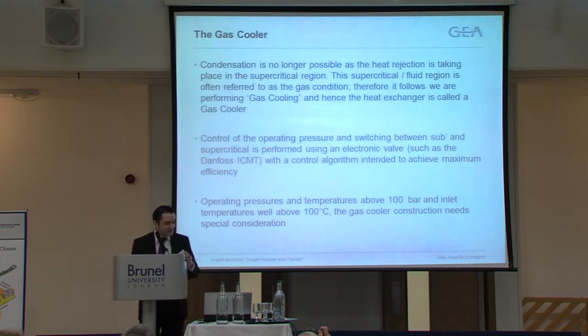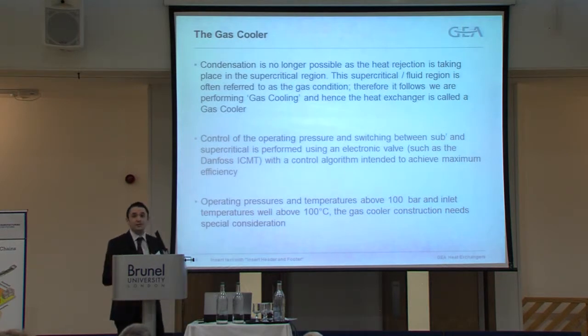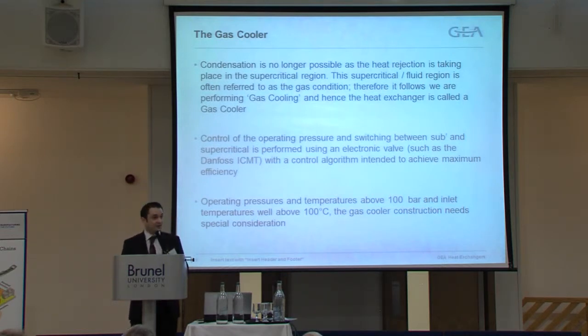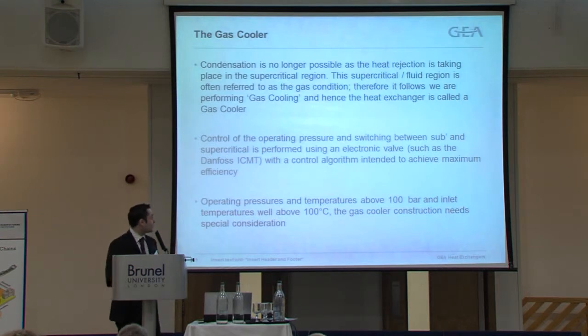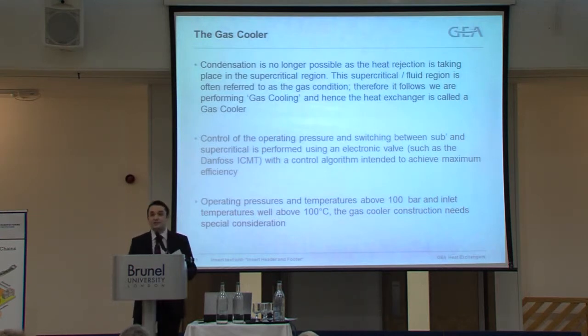So, in summary, condensation is no longer possible because heat rejection is taking place in the supercritical fluid region. Therefore, it's commonly known as the gas region, so it could be said we're completing gas cooling, hence the product's called a gas cooler. Now, control of the operating system between subcritical and supercritical is managed by a valve such as the Danfoss ICMT or the ICMTS, which they'll be speaking to you about later, I'm sure, which works off a control algorithm to ensure the system's always working at the maximum efficiency. Now, with operating pressures above 100 bar and inlet temperatures well above 100 degrees C, a conventional heat exchanger isn't the best bet, and the construction of the heat exchanger needs special consideration.